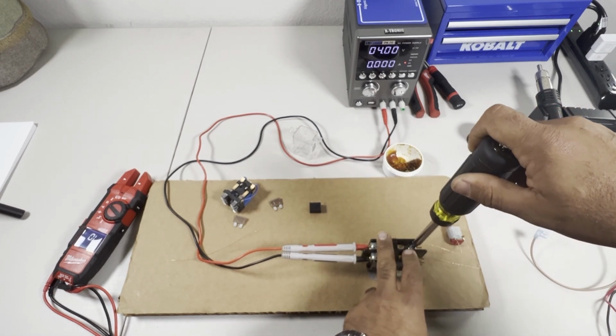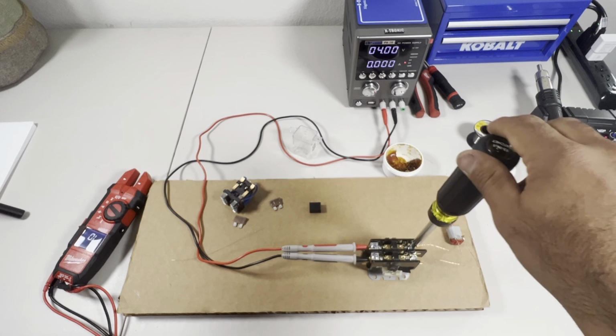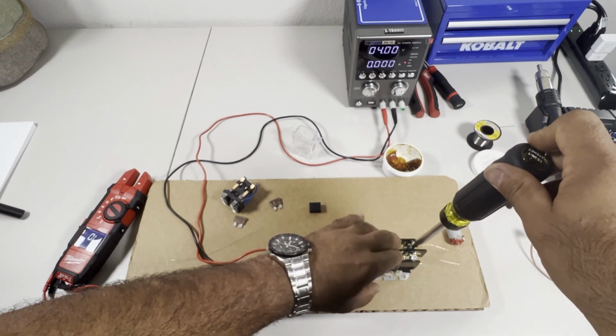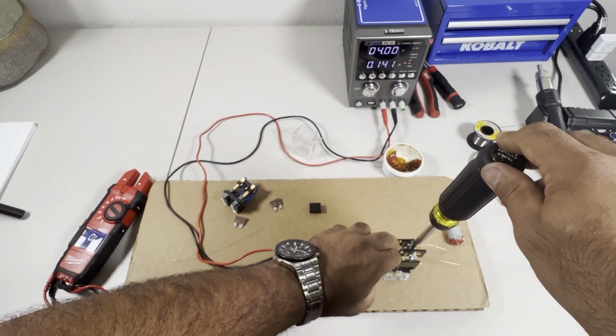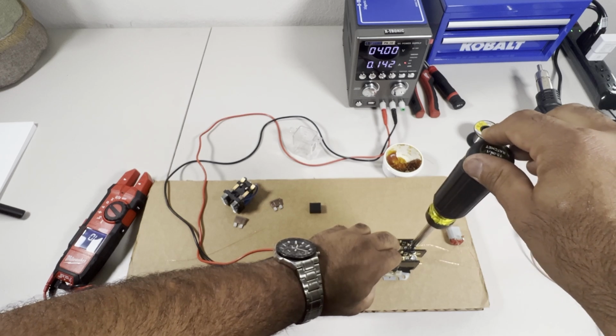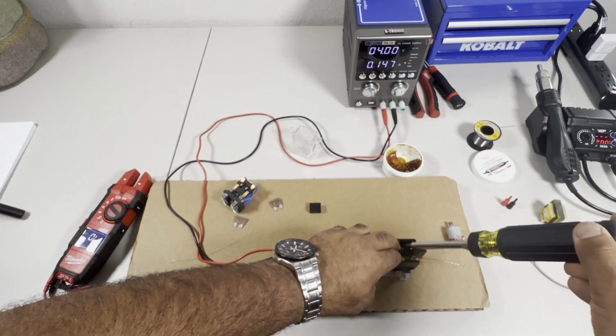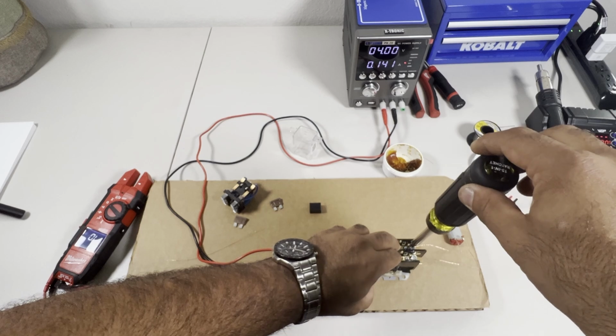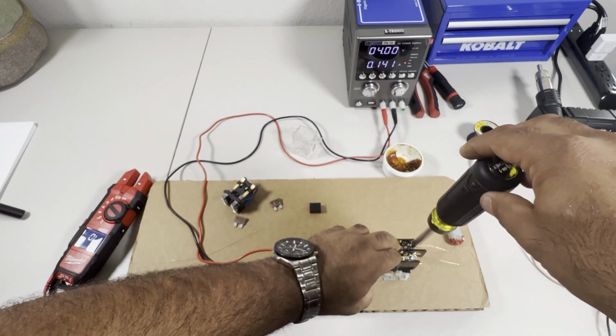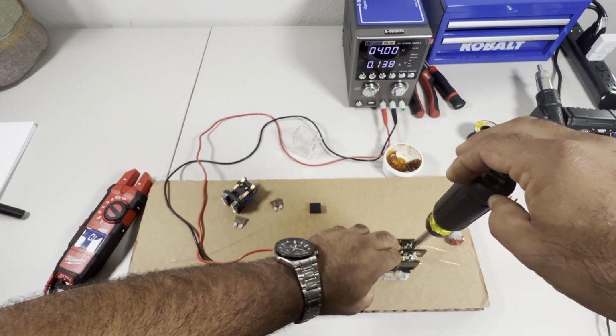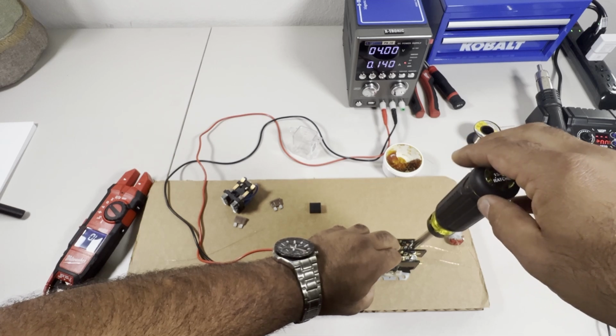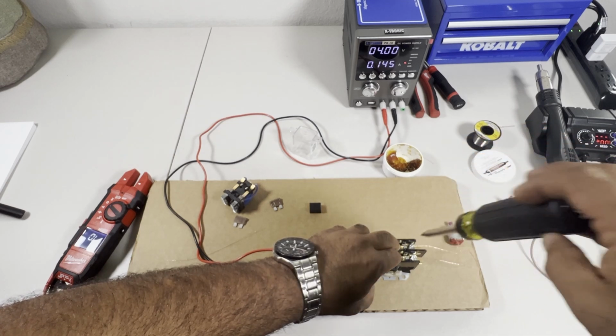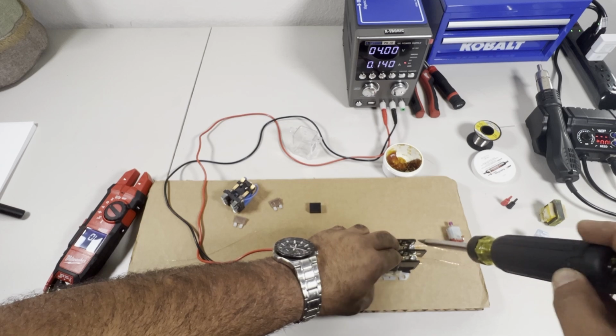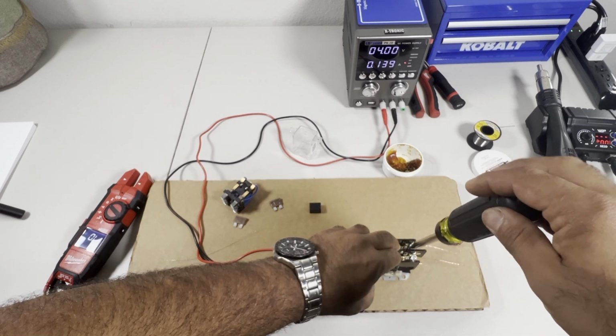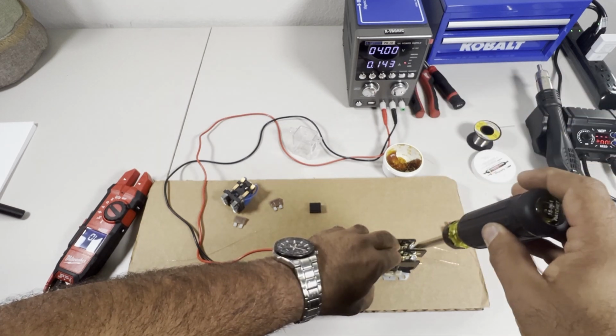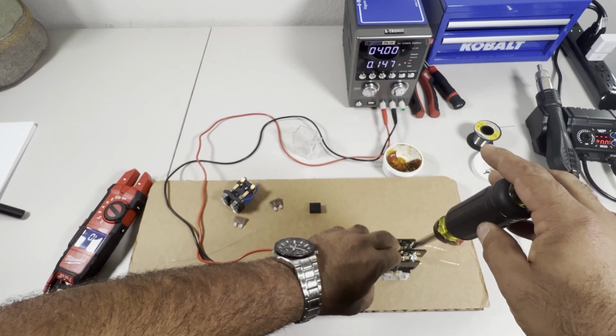I'm going to loosen one of the terminals. Now, we want to take a look at this and pay attention to what happens. Right now, the motor is running. No problem. Everything is good to go. When those contacts are getting damaged, they're going to have this effect on the motor. Can you hear it? The RPM keeps going up and down. And you can see the amperage over there keeps jumping up and down.